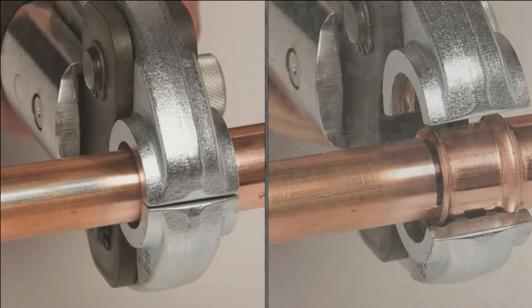Yeah, so this is a common mistake on our fitting too. A lot of guys used to pressing water will try to press on the O-ring because it feels natural to do, but it's completely opposite with ours. The O-ring is just a sealing element that you're cinching in tight, but it's really about that metal-to-metal double circular press that work hardens that joint from soft to hard copper. Once you have that, the O-ring is just there to seal. It's not for strength, it's nothing.